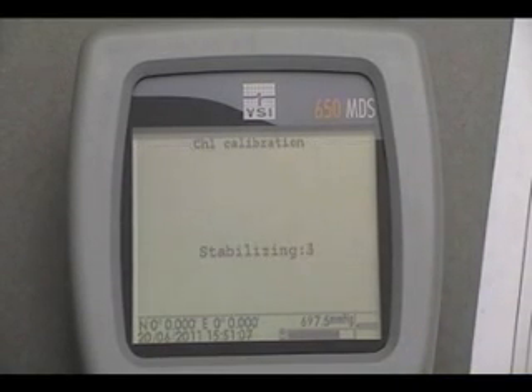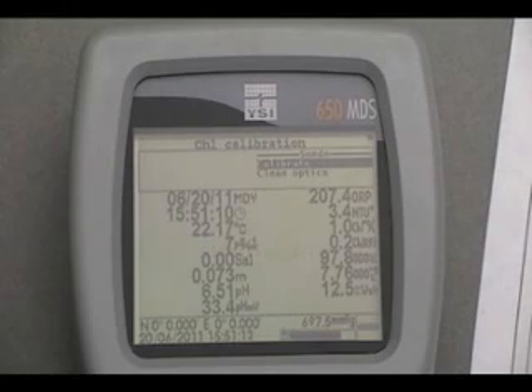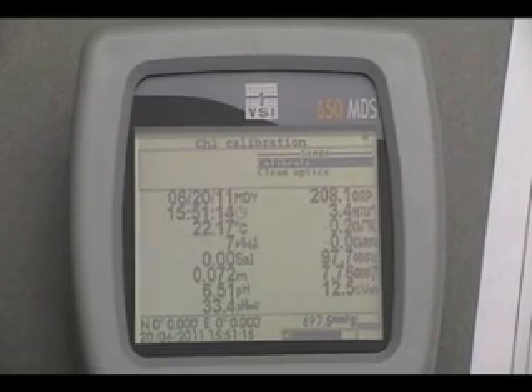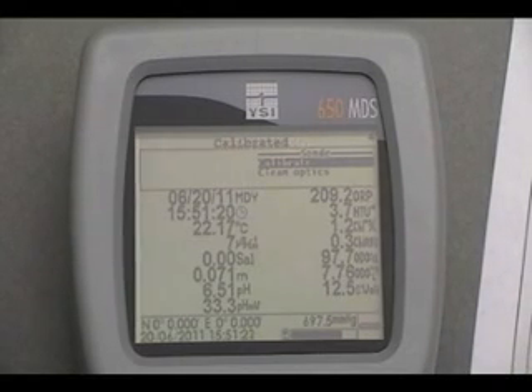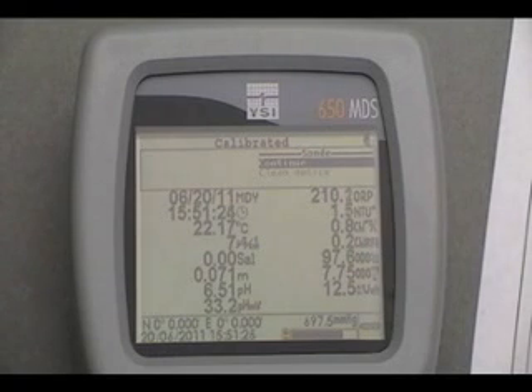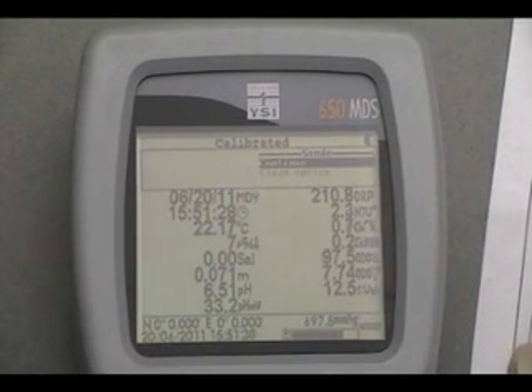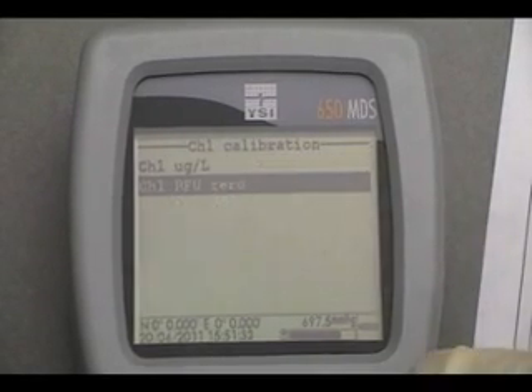Step 6. When the readings have stabilized, record the pre-calibration chlorophyll reading on the calibration sheet. Press Enter to confirm the calibration and zero the sensor. Step 7. Record the post-calibration chlorophyll reading on the calibration sheet. Press Enter to continue and Escape to return to the main menu.